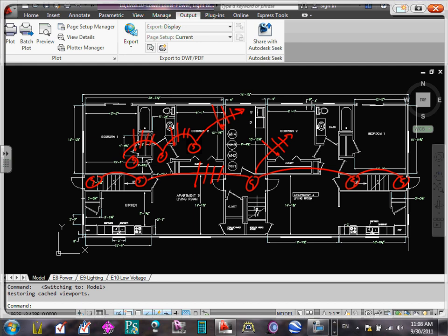Is the entire building commoned out for the fire? So if I start a fire in my kitchen, my neighbors will wake up too? No, not this. That might be a very good point. That might be a building issue here, the way we're designing it. I believe you can get away with this. What's the alternative? The alternative is to have a low voltage fire alarm system for the whole building, or from the common panel. But what we're going to do is not interconnect the apartments with the common areas.